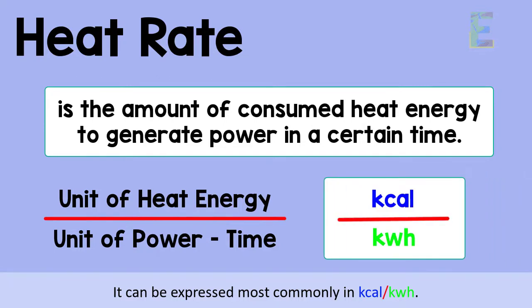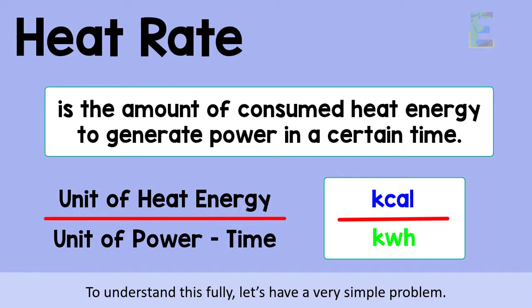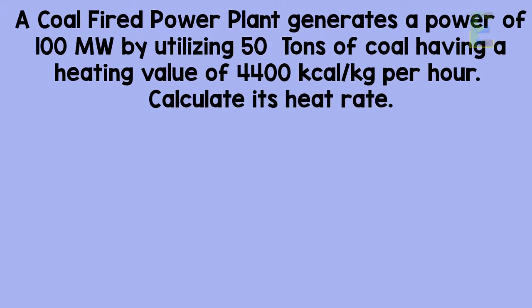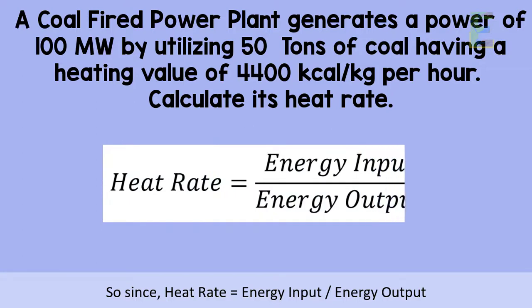It can be expressed most commonly in kilocalories per kilowatt hour. To understand this fully, let's have a very simple problem. A coal-fired power plant generates a power of 100 megawatts by utilizing 50 tons of coal having a heating value of 4400 kilocalories per kilogram per hour. Now, calculate its heat rate.